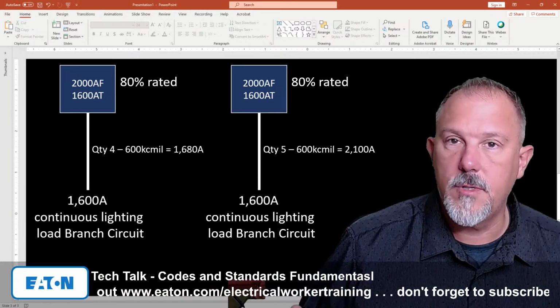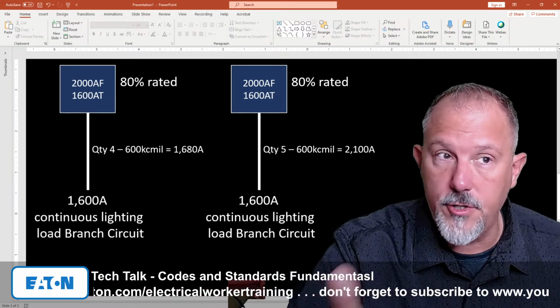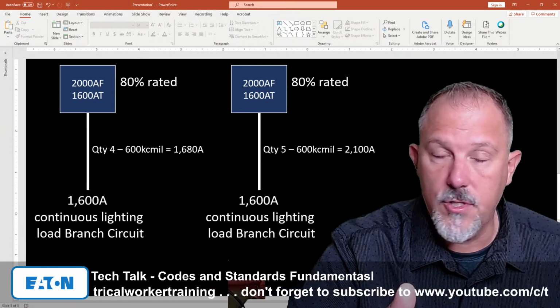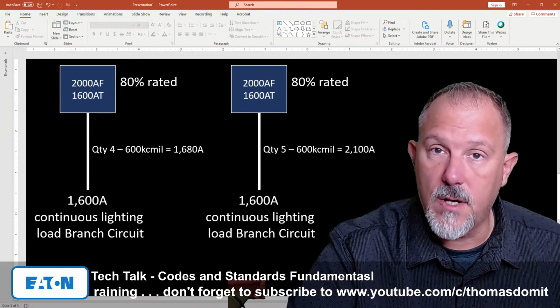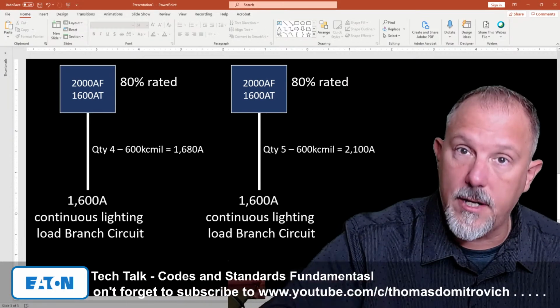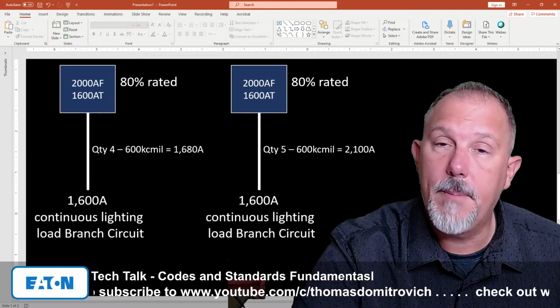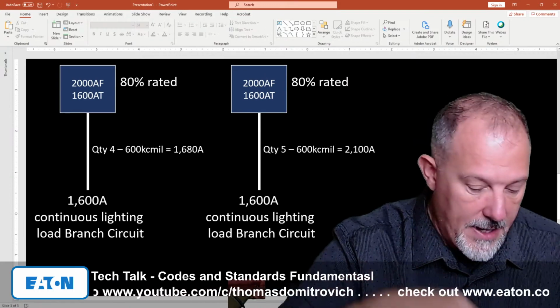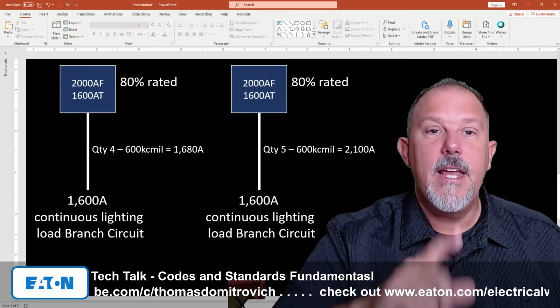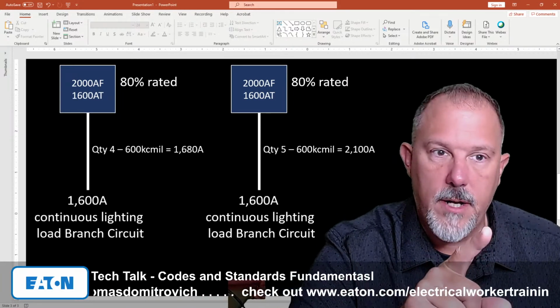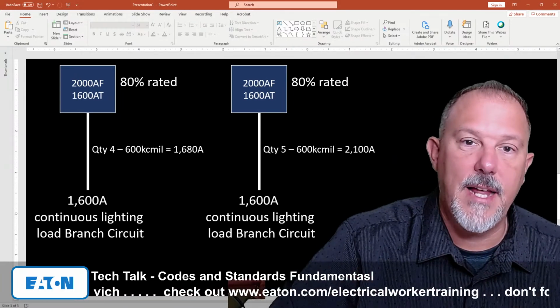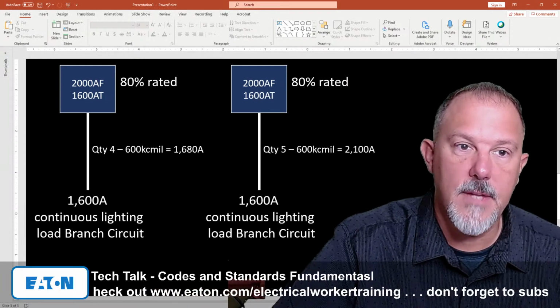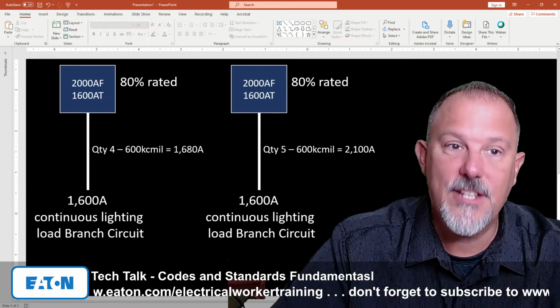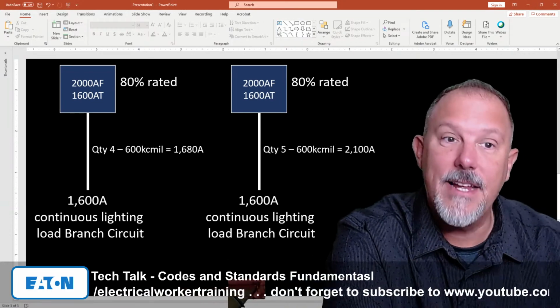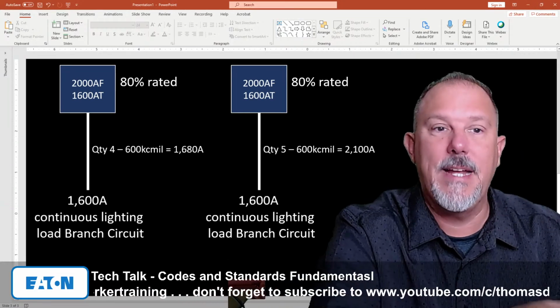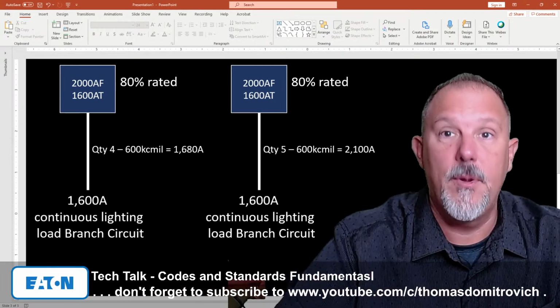And then 4 is password protected. If you recall, on Tuesday, I talked about circuit breakers and I showed you those electronic breakers and our new Power Defense breakers that had the password protection. That would fall under 4. So if I have a 2000 amp frame circuit breaker adjusted to 1600 amps, and I lock the cover, it's no longer a 2000 amp rated breaker. It's now a 1600 amp rated breaker.